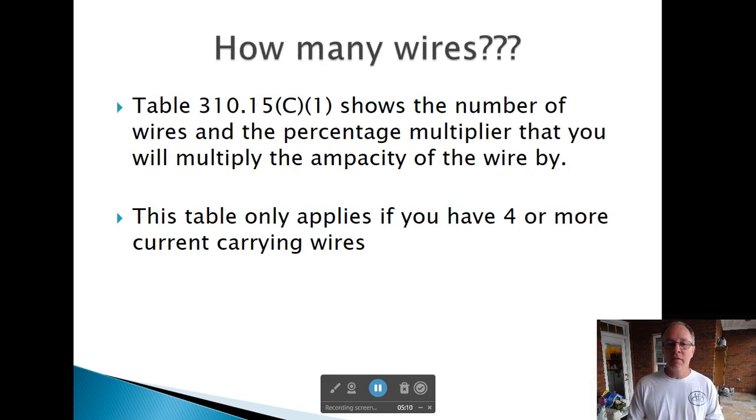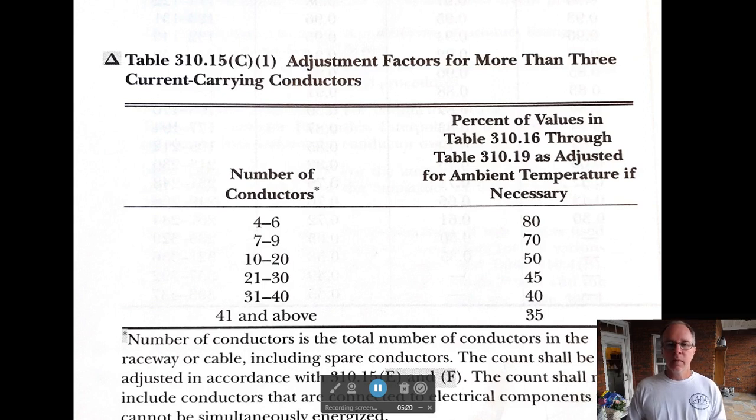We've got to de-rate it. So basically you're saying, okay, we're not going to jump as much because we're not allowed to. So how many wires? We've got to go to Table 310-15-C1, and that shows the number of wires and the percentage multiplier that you will multiply the ampacity by. As you can see here, one to three wires is at 100%, but that's already on Table 310-16. We're looking for seven to nine conductors, which is 70%. So we're going to take that amperage and multiply it times 70%.